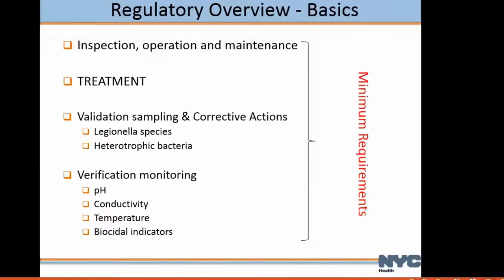Before the regs were in place, there were cooling tower systems that probably had no treatment to kill bacteria and Legionella. The regulations required validation sampling and corrective actions for Legionella and heterotrophic bacteria. They also require verification — that record-keeping piece. Tell us what you're going to do; these are all the minimal requirements.